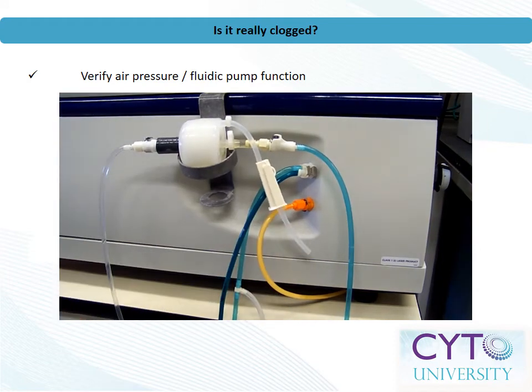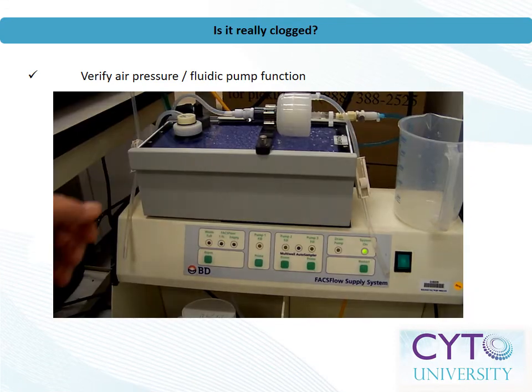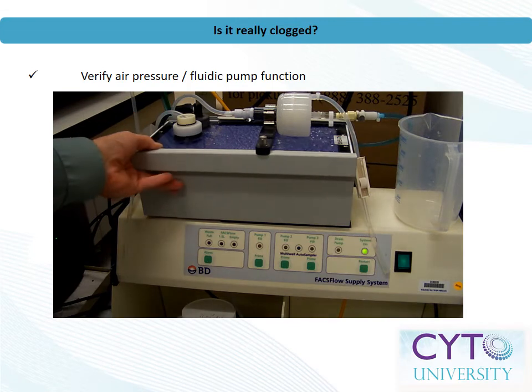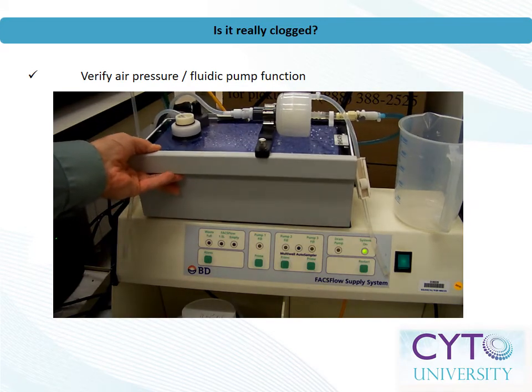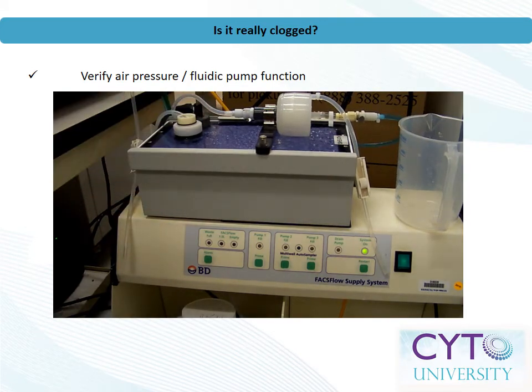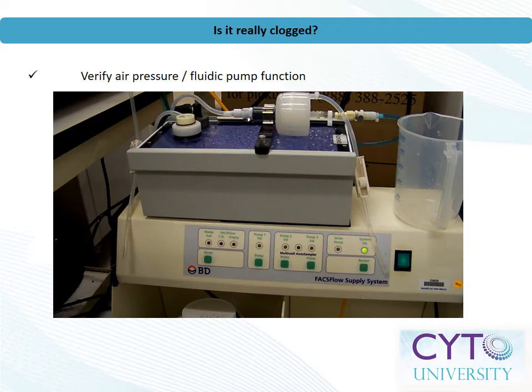Back pressure can sometimes mimic clogs. You'll want to be sure that the system has pressure, or that the fluidics pump system is functioning properly. For air pressure-driven systems, check the pressure gauge, or otherwise listen for an audible hiss when pressure is released. For systems relying on a wet cart or fluidics pump, be sure the last user reset the system after refilling the sheath fluid.